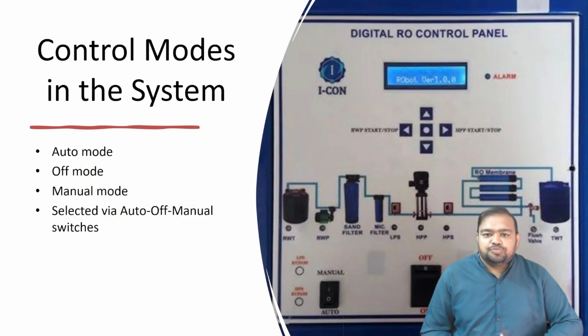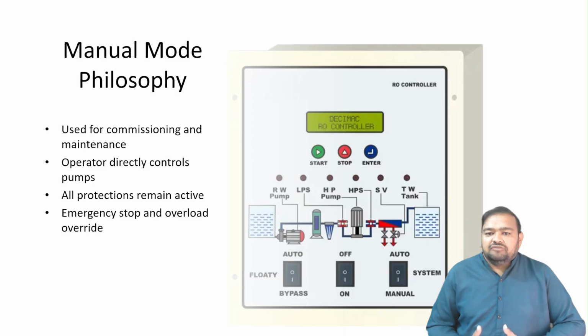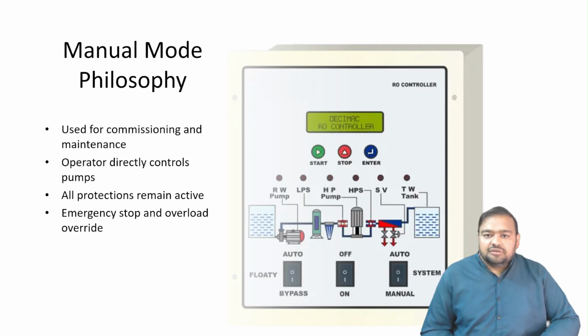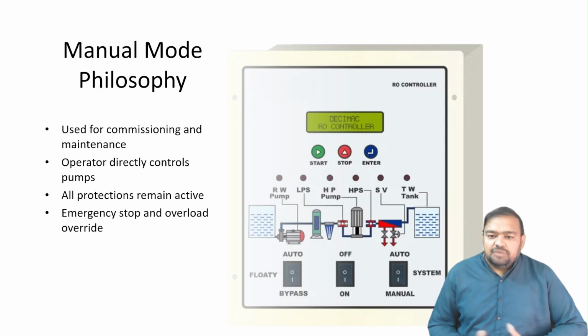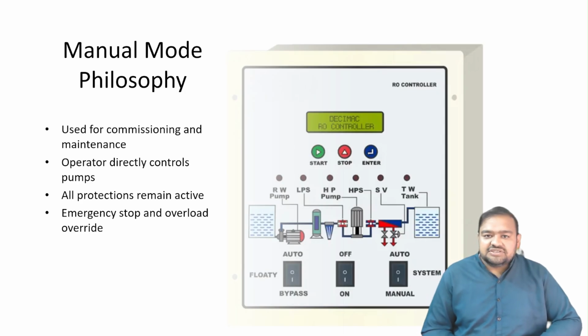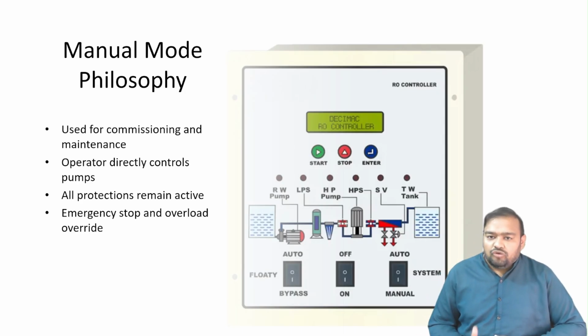In our system, each pump operates in three modes: auto, off, and manual mode. These modes are selected using auto, off, manual selector switches on the panel door. Let's start with the manual mode. Manual mode is typically used for commissioning, maintenance, and troubleshooting. In manual mode, the operator can start or stop the pump directly. However, all safety interlocks remain active. Overloads, emergency stop, and phase failure must always trip the pump. Manual mode never means unsafe operation.